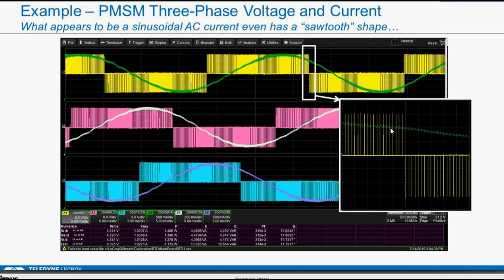Notice this current waveform. This is pretty interesting. A lot of people don't see this. This looks like noise, but it's not noise. That current is always increasing a little bit whenever the pulse width is high, and when the pulse width goes low, the current starts to drop, and then it starts increasing again. So it's kind of like a charge discharge, treating the winding as kind of a source, with charge and discharge happening as pulse width voltage is applied, taken away, reapplied and taken away. So it's kind of interesting. Even this sine wave that looks mostly not distorted really does have a very high level of distortion on it.